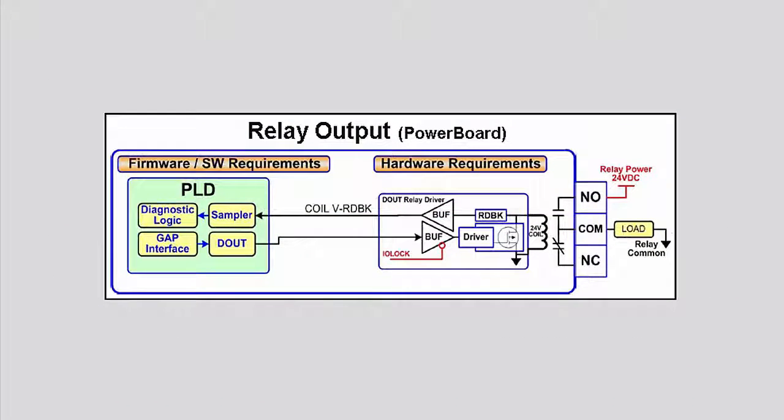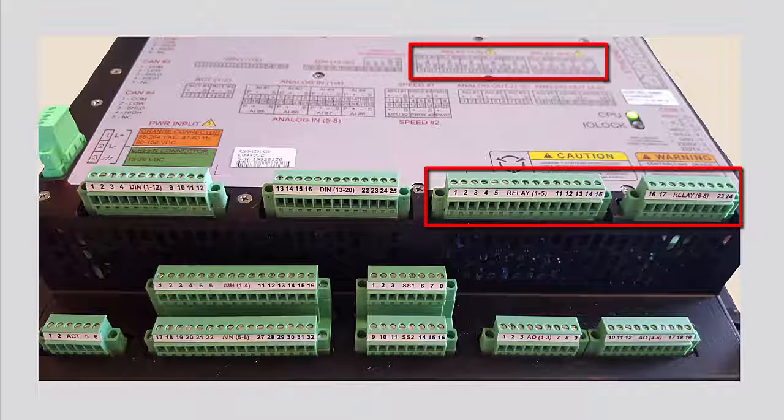Discrete or relay outputs on the controller are isolated and use form C relay outputs with normally open, normally closed, and common contacts. Each individual relay is separated into a numbered block containing the contact labels and corresponding terminal block numbers.